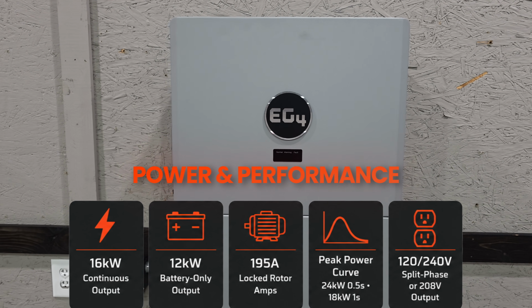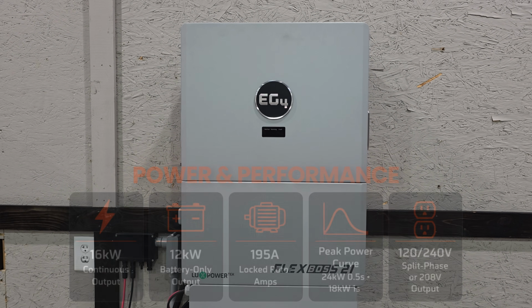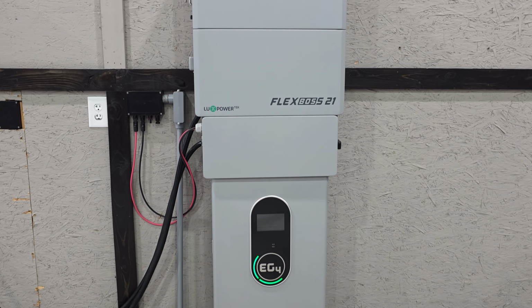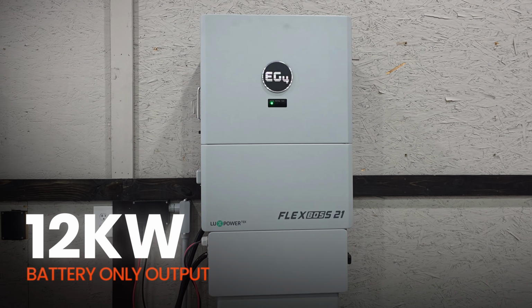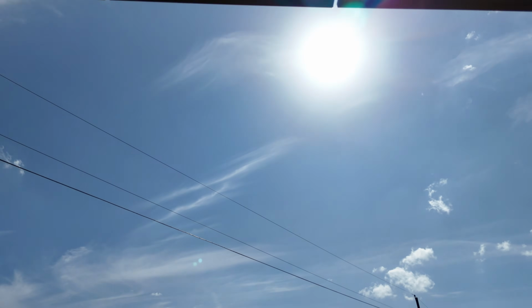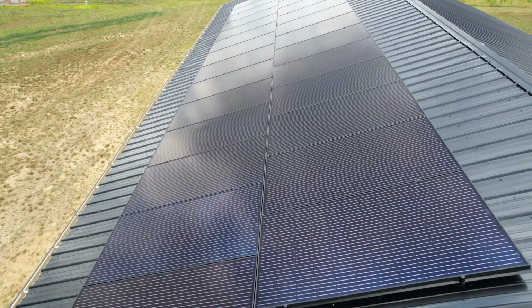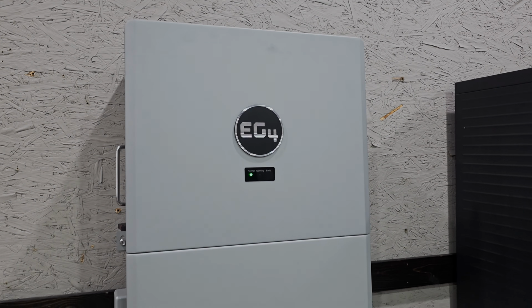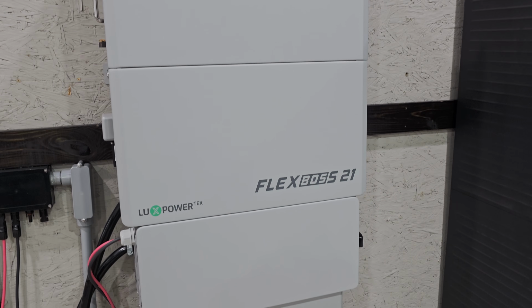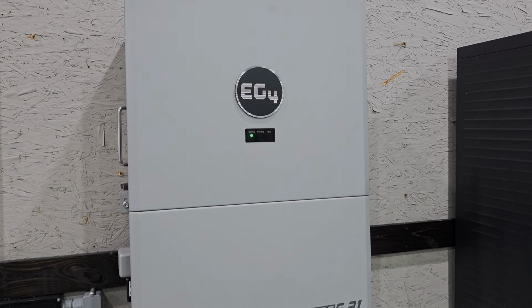The FlexBOSS 21 is rated for 16 kilowatts of continuous output when paired with PV and battery. That is a lot of usable power for a residential hybrid inverter. Now, the important detail here is that battery only output is a little bit lower. Battery only with the FlexBOSS 21 is rated at 12 kilowatts of continuous output. And that matters because when the sun is out and the system has solar available, you can take advantage of the higher output capacity. But when you're running the battery alone, you need to understand the 12 kilowatt number. That is still a strong amount of power. It can support a lot of typical home backup loads, but it's not the same as saying the inverter can give you 16 kilowatts of continuous output from the battery alone. The distinction matters, especially if you're comparing this to other inverters.